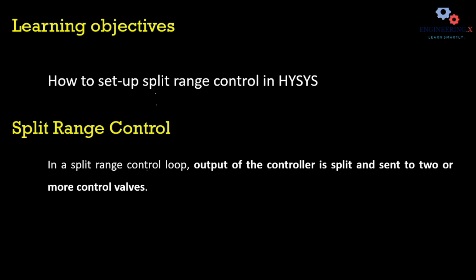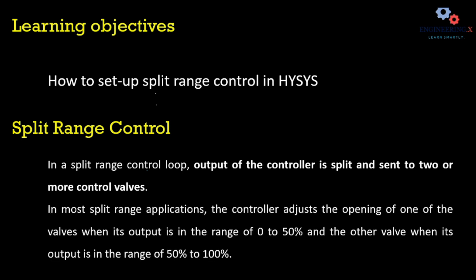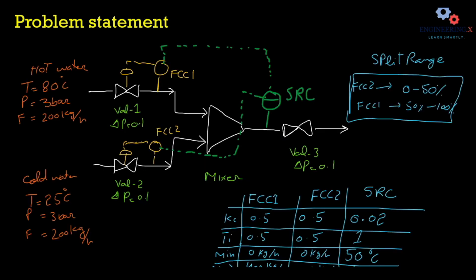Let's start first with split range control. In this control loop, the output of the controller is split into two or more percentages that are sent to the final control element — it could be a control valve or any other element — to control the process variable. In most split range applications, the controller adjusts the opening of one valve when its output is in the range of 0 to 50 percent, and the other valve when its output is in the range of 50 to 100 percent.